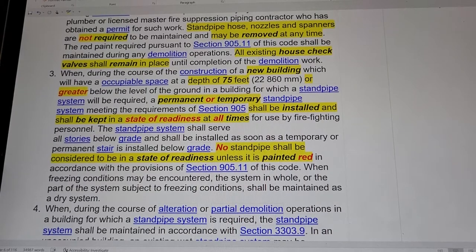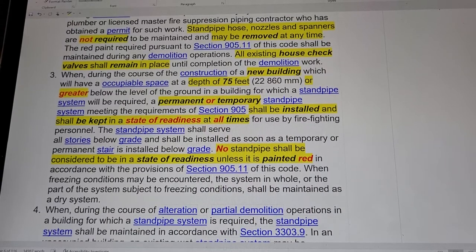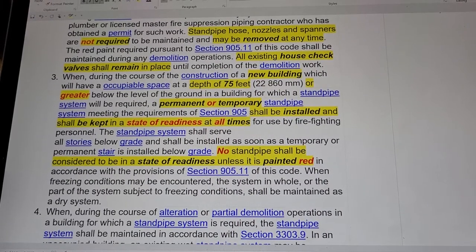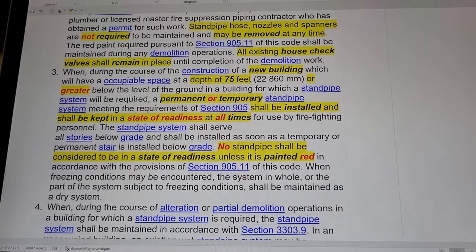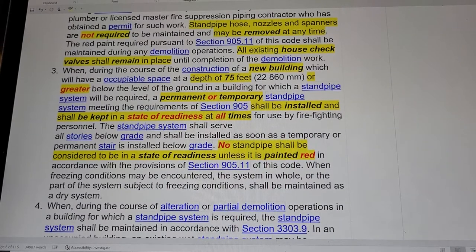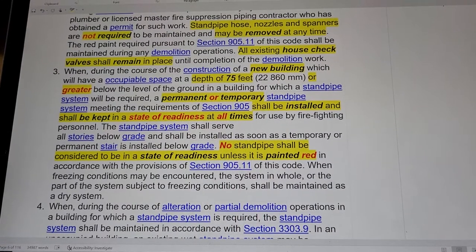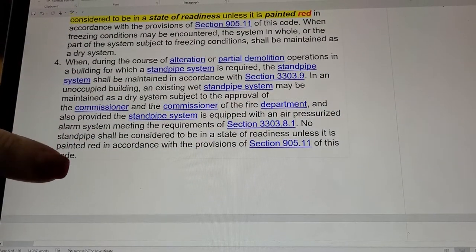During the construction of a new building with occupiable space at a depth of 75 feet or greater below ground level, where a standpipe system is required, a permanent or temporary standpipe system meeting the requirements of section 905 shall be installed and kept in a state of readiness at all times for firefighting personnel. The standpipe shall serve all stories below grade and shall be installed as soon as temporary or permanent stairs are installed below grade. No standpipe shall be considered in a state of readiness unless it is painted red, and under freezing conditions it shall be a dry system.